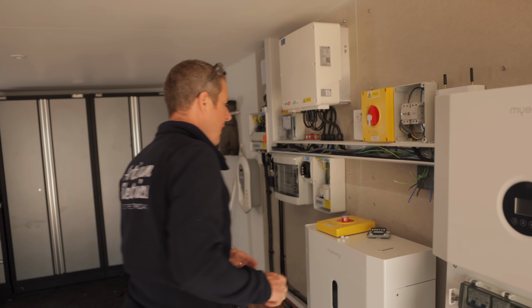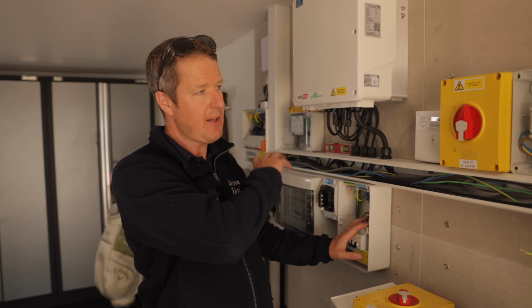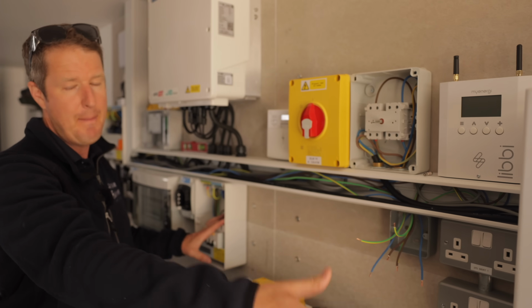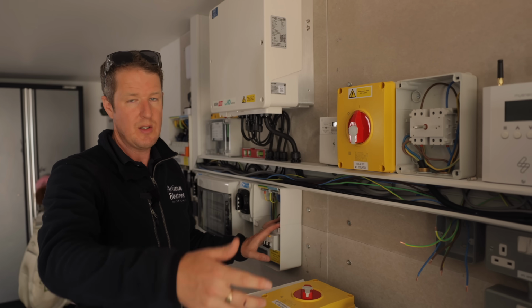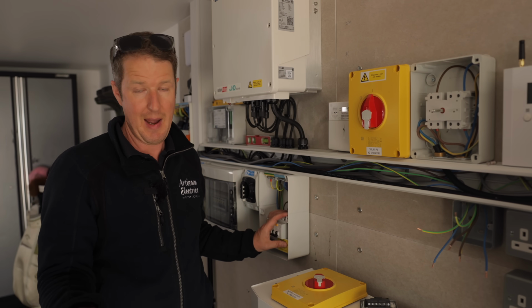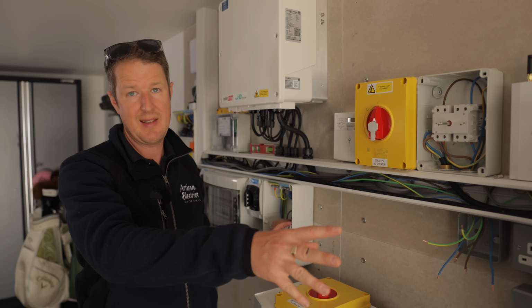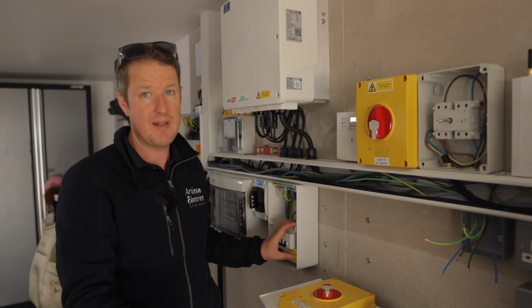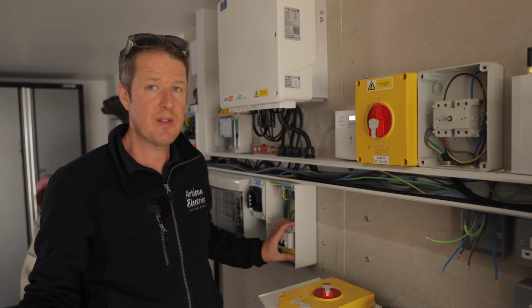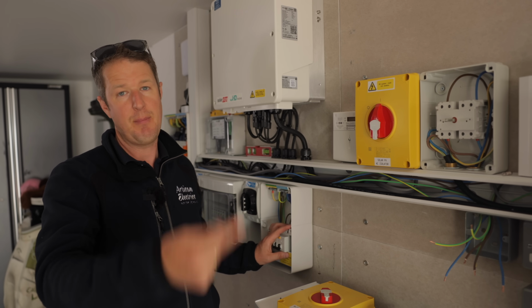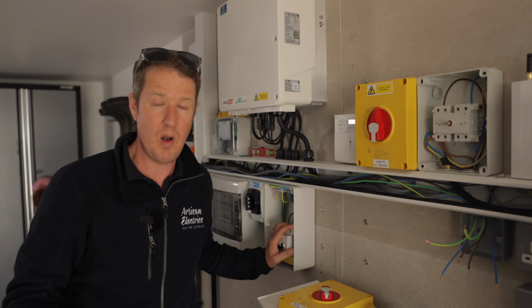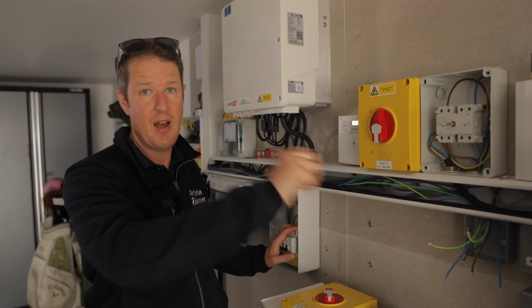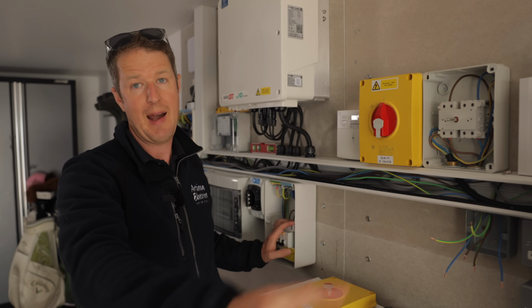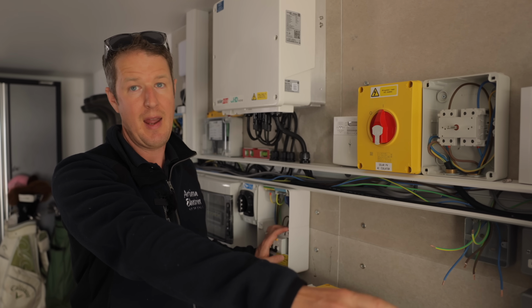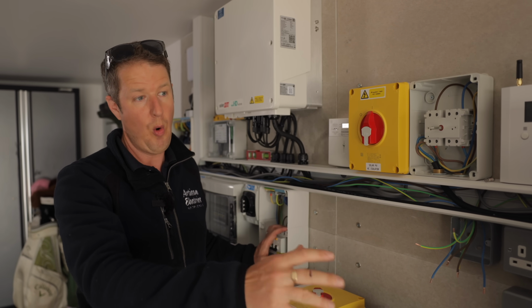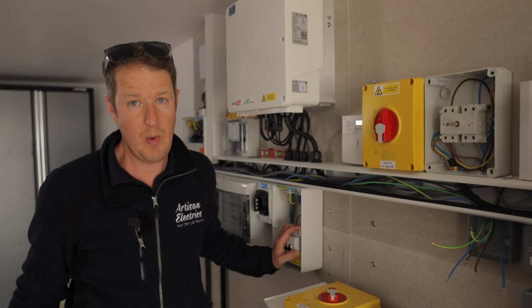When you're designing the install, remember that if you're running backup power, you need to size the supply to the input side, to the grid side of the inverter, suitably that it can cope with the inverter load plus the backup loads. So for example, if you're running a 3.68 kilowatt inverter with 3.68 kilowatts of backup loads, for argument's sake, you would need to size the supply cable that it could cope with 7.36 kilowatts of power at any one time, because the inverter could be pulling and charging the batteries, but also the backup loads will still be running. So that feed cable that's supplying the Libbi inverter will be running at more than just the rating of the inverter. It will have the backup loads running through it as well.